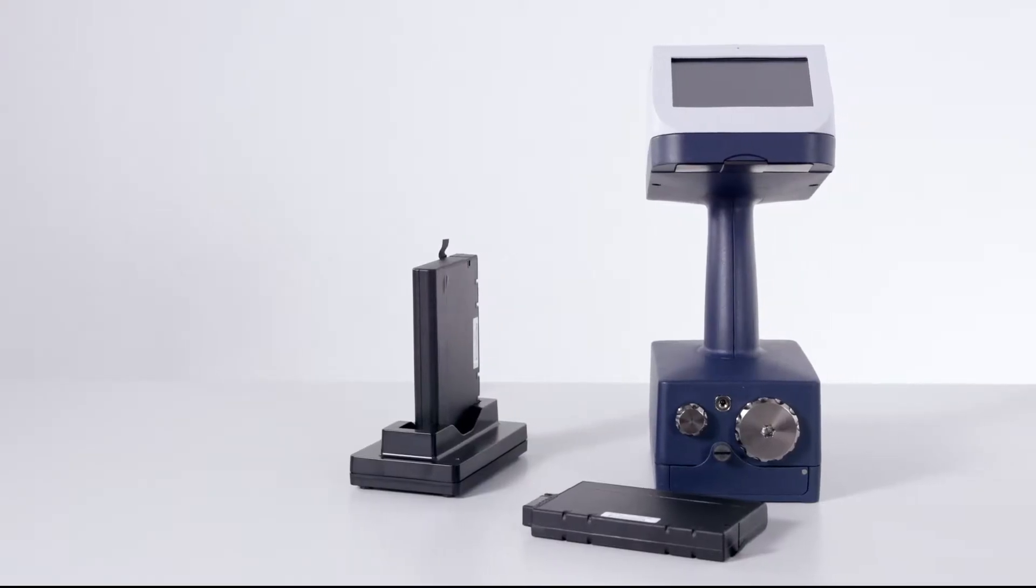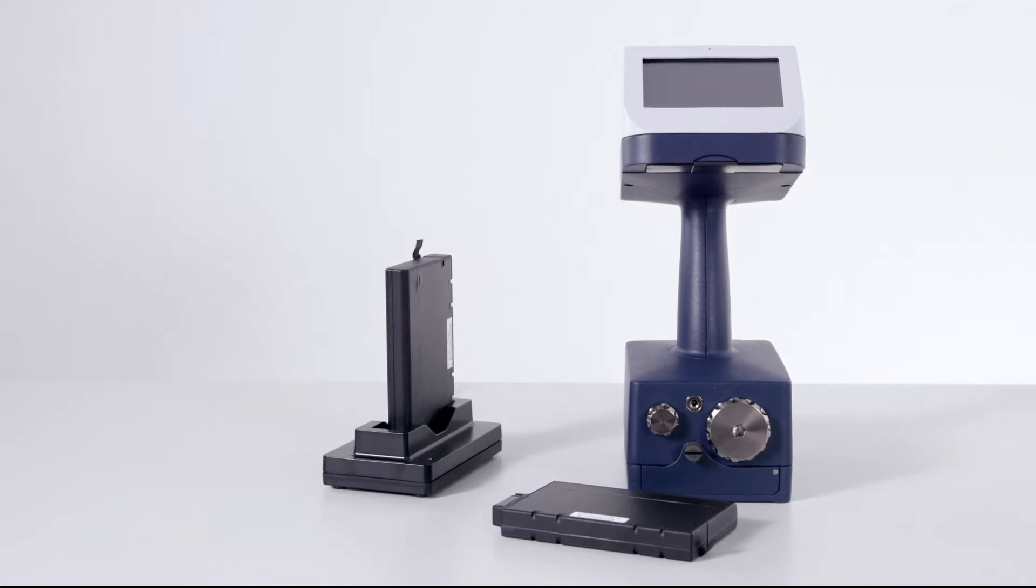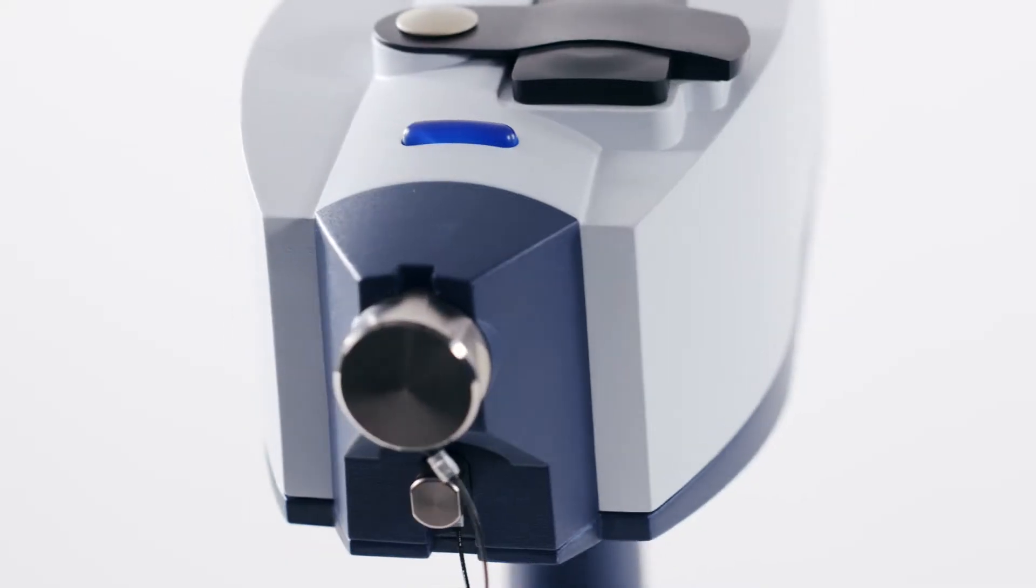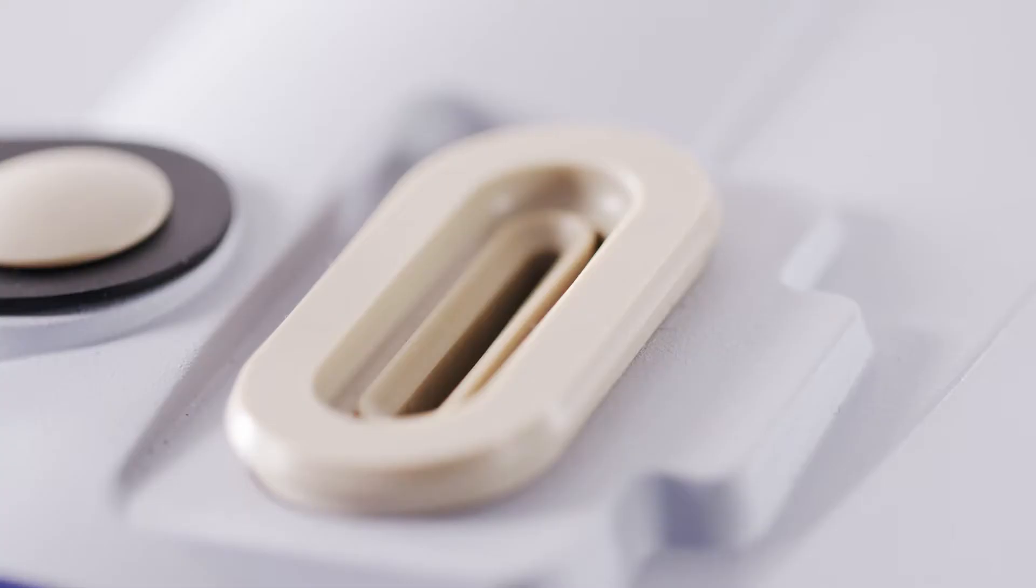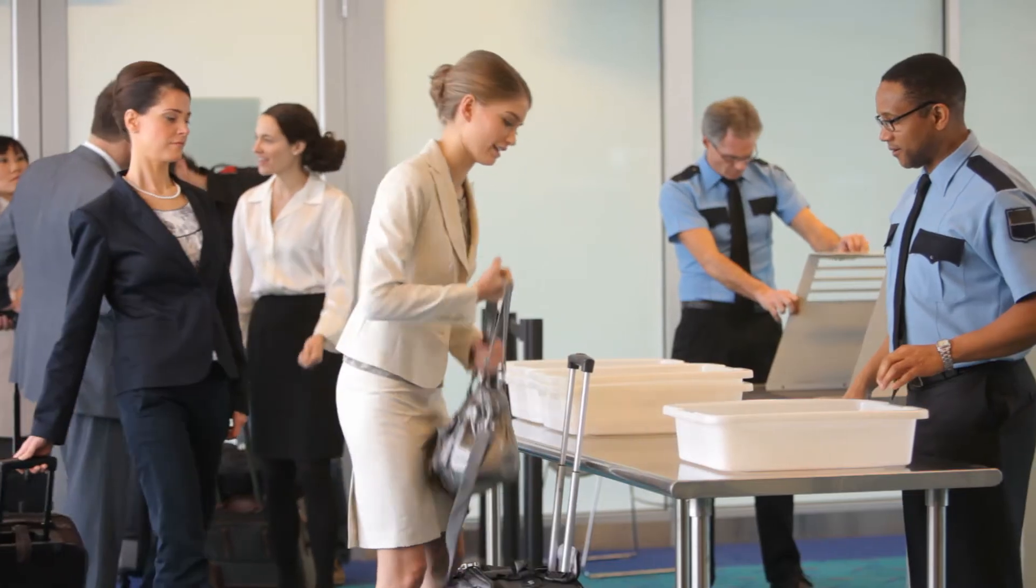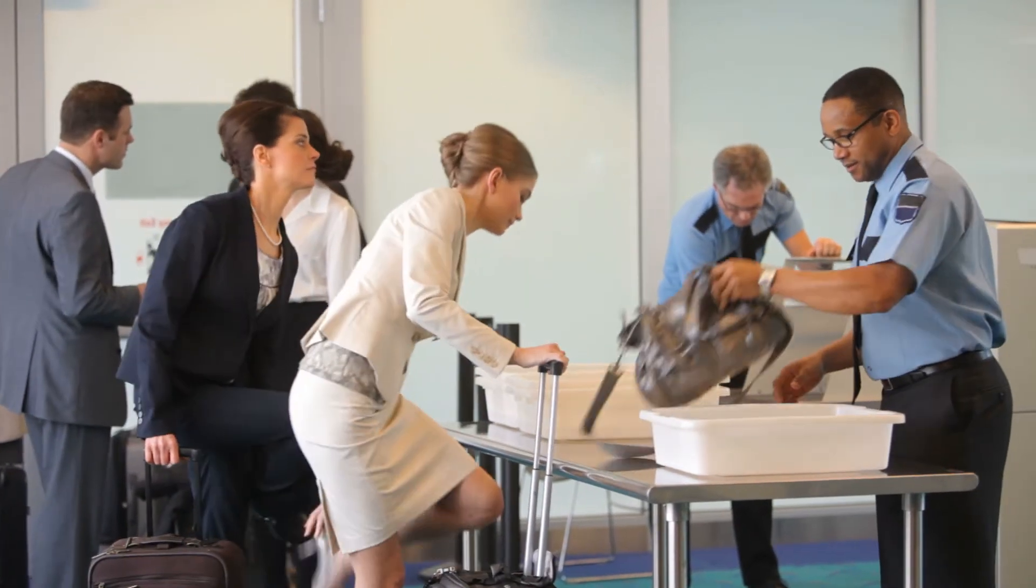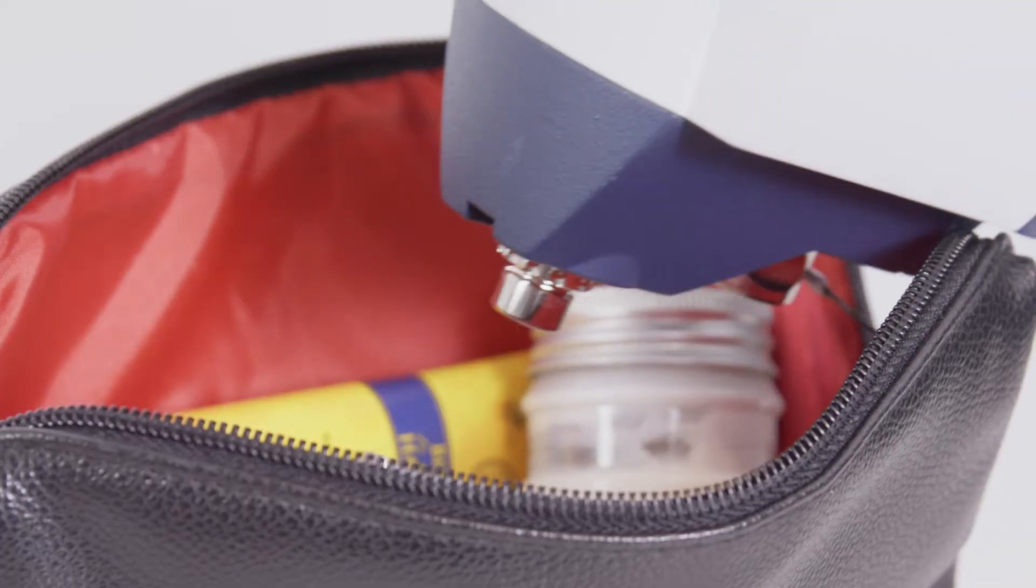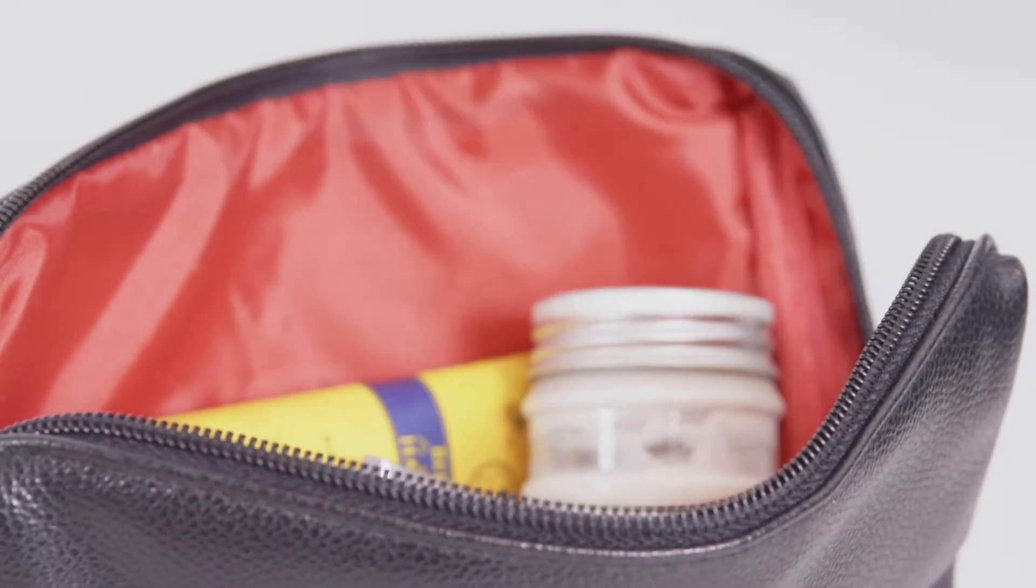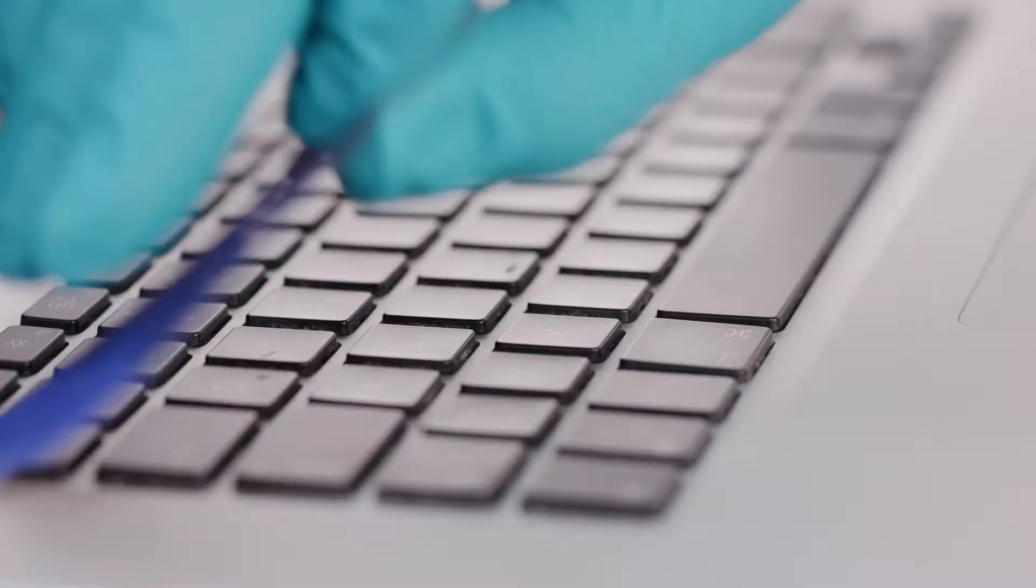The Bruker Roadrunner is battery powered, lightweight and portable. The Roadrunner operates in two modes, sniff and swab. The sniffer mode draws in vapors from volatile explosives and taggants and displays results in seconds using intuitive software on the touch screen.